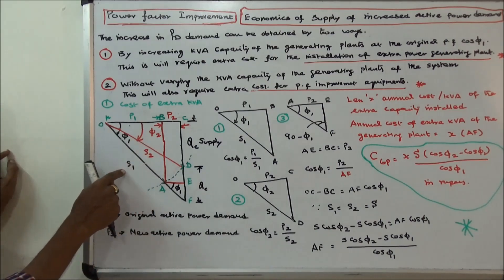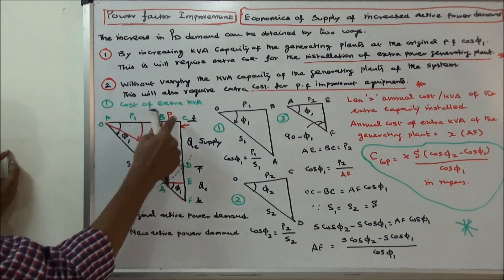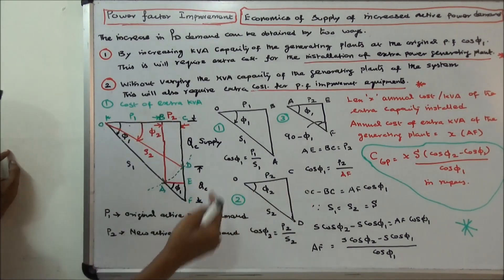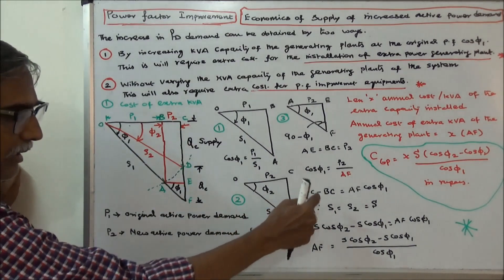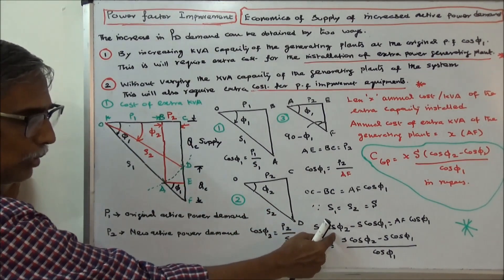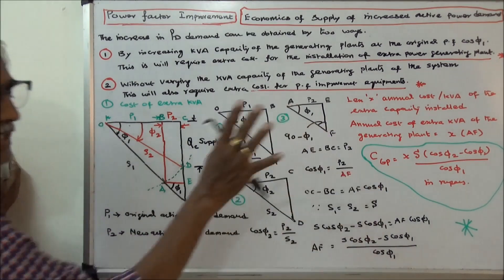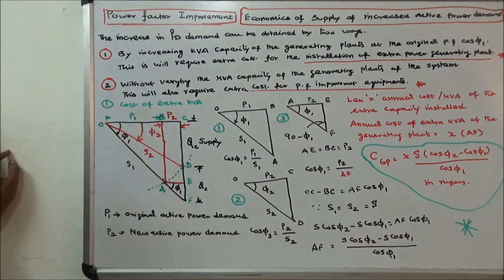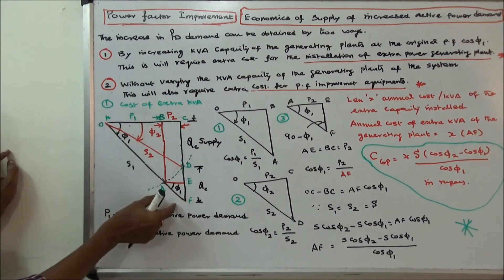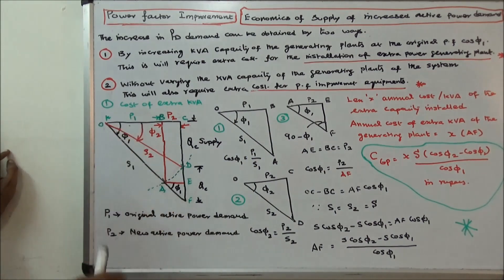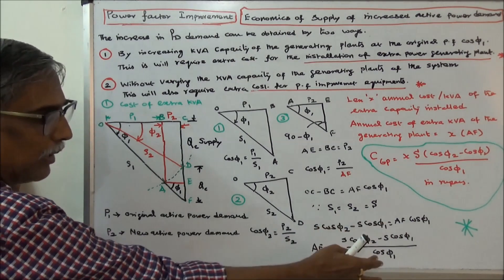We are keeping S1 equal to S2. Here, OC minus BC equals AF into cos phi 1. OC is S into cos phi 2, and BC is S into cos phi 1. That gives AF into cos phi 1. Therefore, AF — the rating of the additional generating plant — is equal to S into (cos phi 2 minus cos phi 1) divided by cos phi 1.